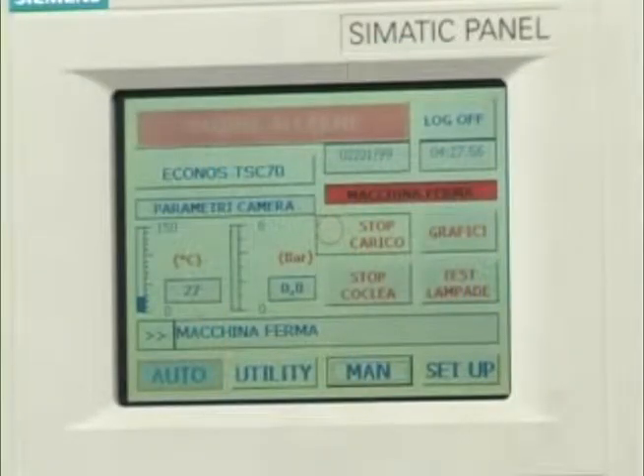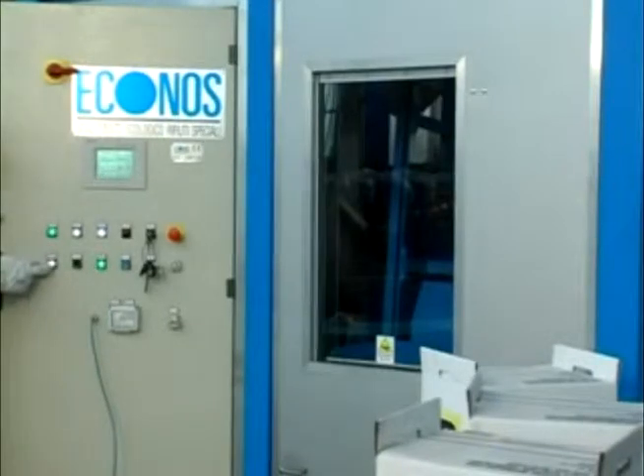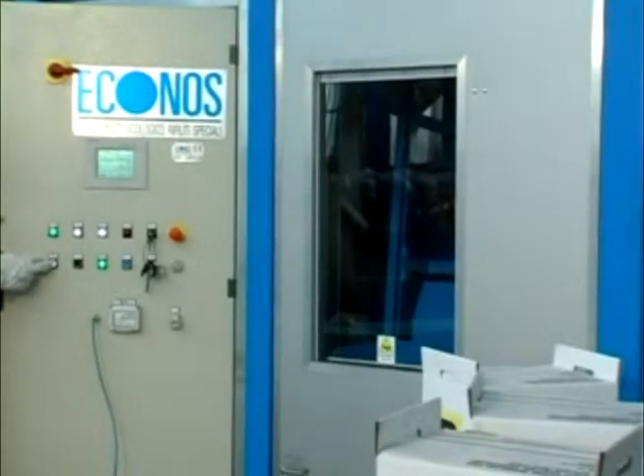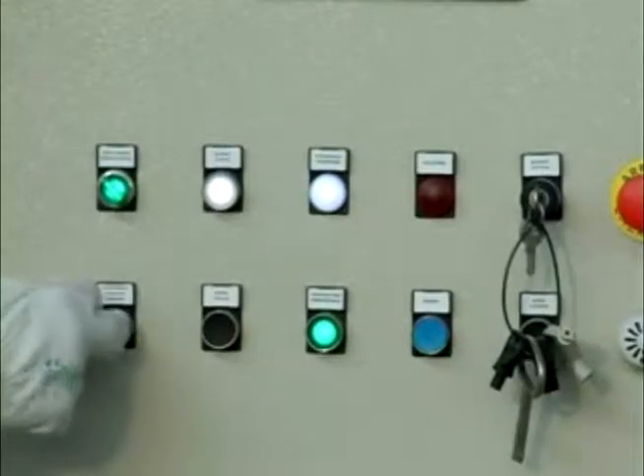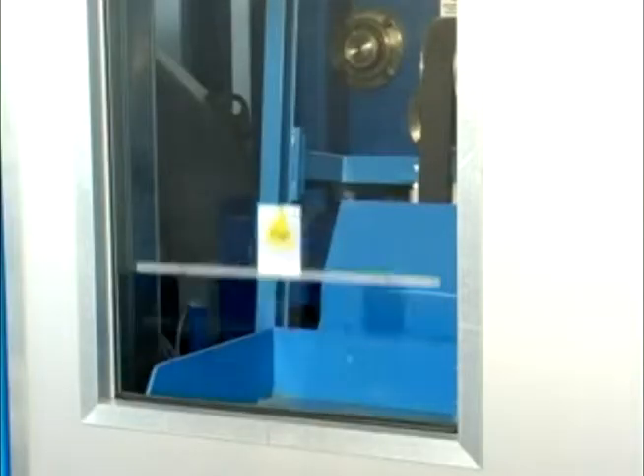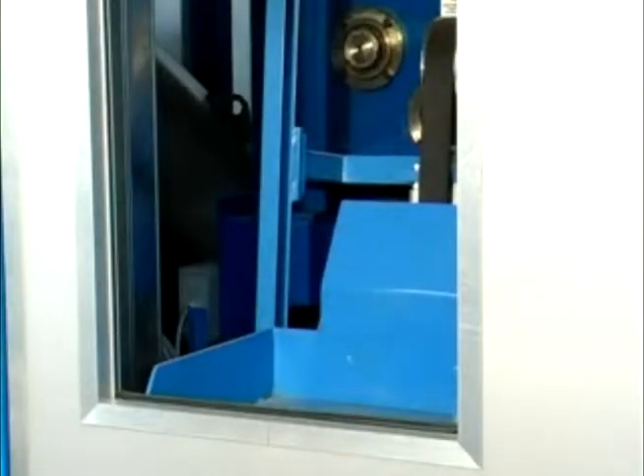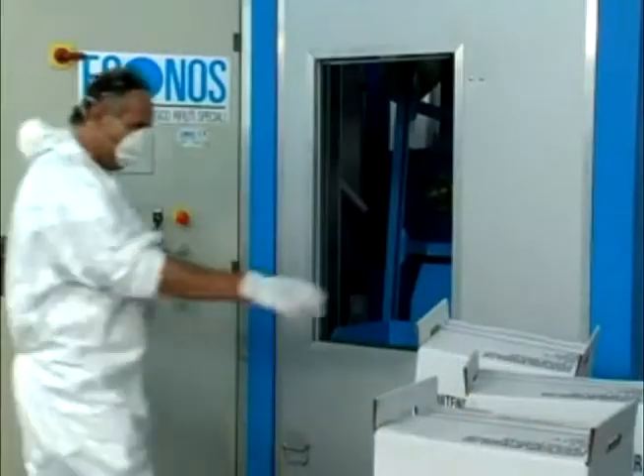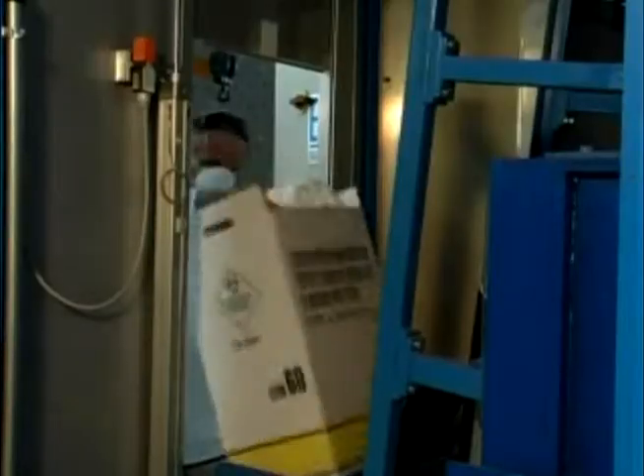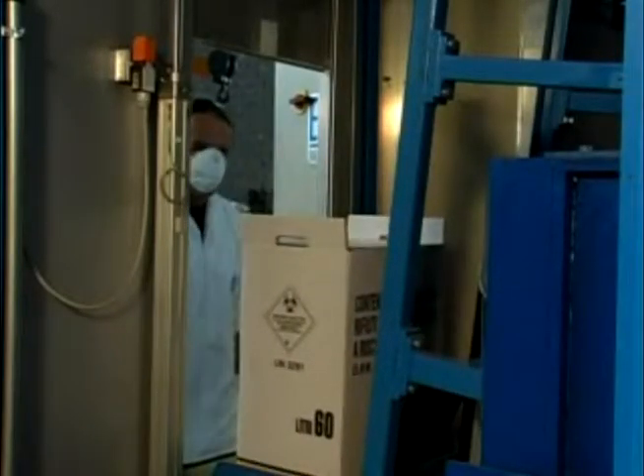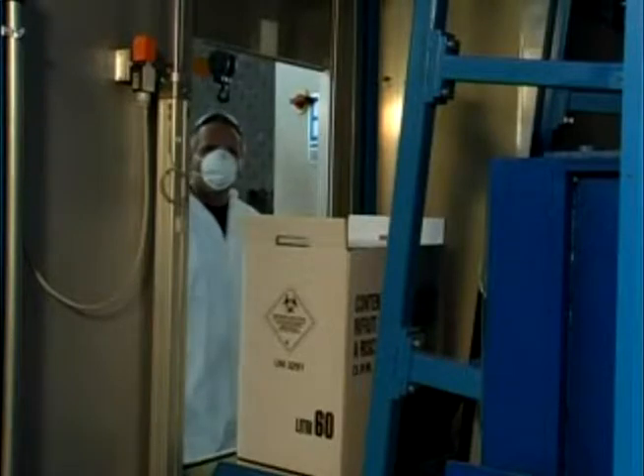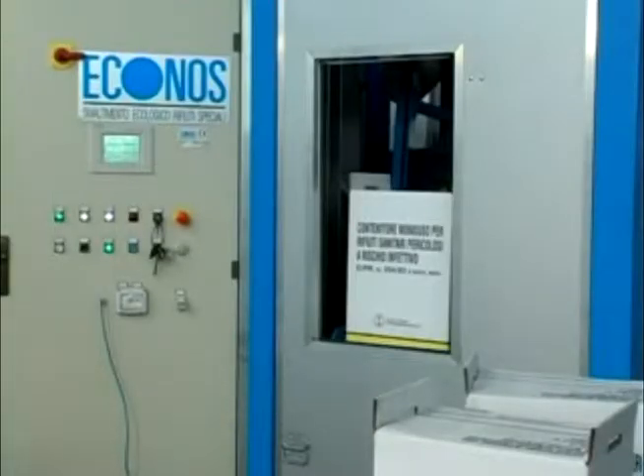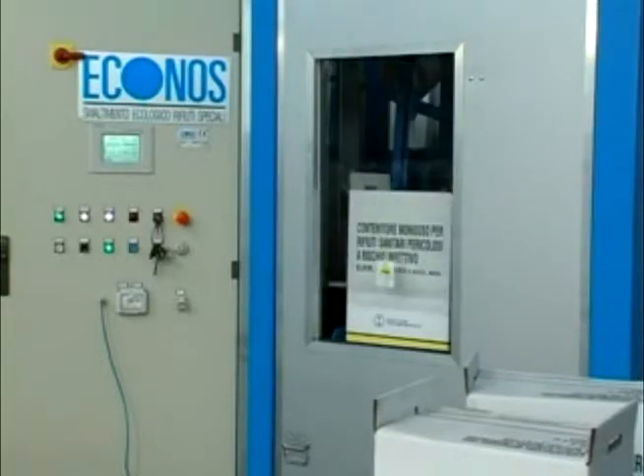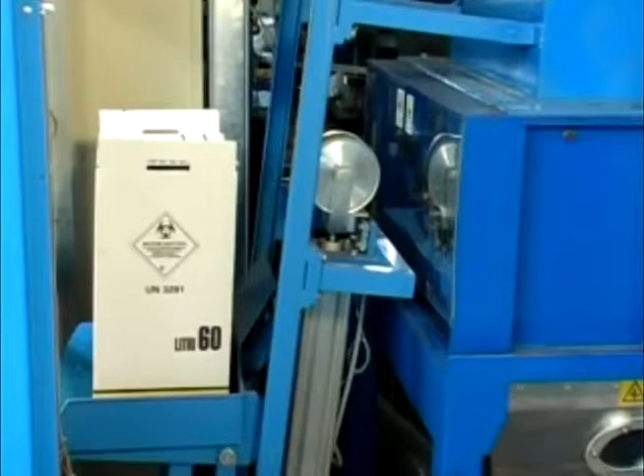How the Econos system works. When the operator has been notified by a flashing light located on a control panel, he presses the button that opens the loading hatch and places the waste into the lift system. By this time, the operator has no further contact with the special waste. The subsequent treatment phases are carried out automatically. Then the waste loses its potential infectiousness.